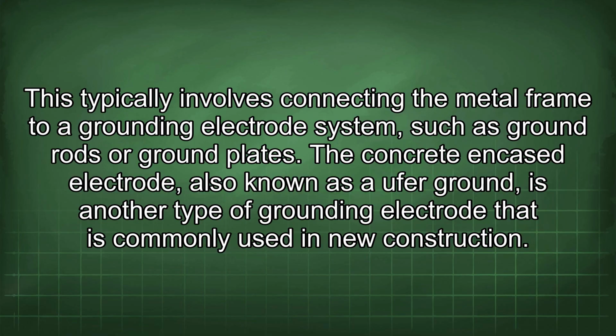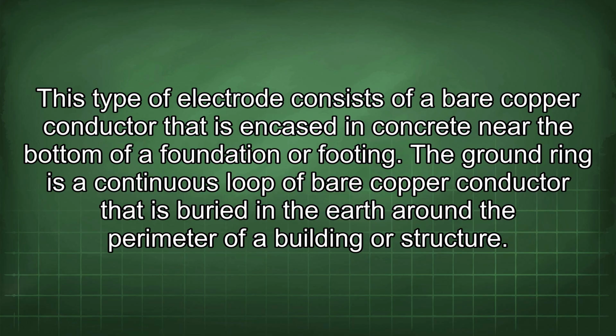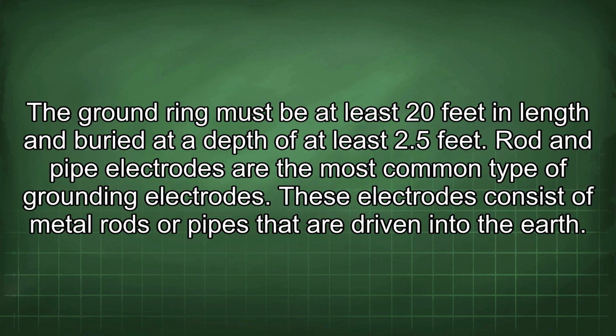The concrete encased electrode, also known as a Ufer ground, is another type of grounding electrode that is commonly used in new construction. This type of electrode consists of a bare copper conductor that is encased in concrete near the bottom of a foundation or footing. The ground ring is a continuous loop of bare copper conductor that is buried in the earth around the perimeter of a building or structure. The ground ring must be at least 20 feet in length and buried at a depth of at least 2.5 feet. Rod and pipe electrodes are the most common type of grounding electrodes.